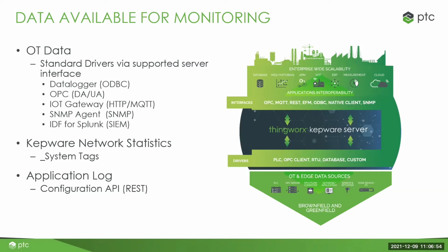And last but not least, we have the events log, which is very useful for troubleshooting, especially for the OT people. Usually we use it to troubleshoot connectivity issues. Things like this can also be leveraged for anomaly detection, to see whether there's any unauthorized access, or anyone who opened the configurator that is not supposed to, login failures, things like that. Those are all logged into the events log. So there's a way to actually extract that through the configuration API. So that will be the coverage on that.